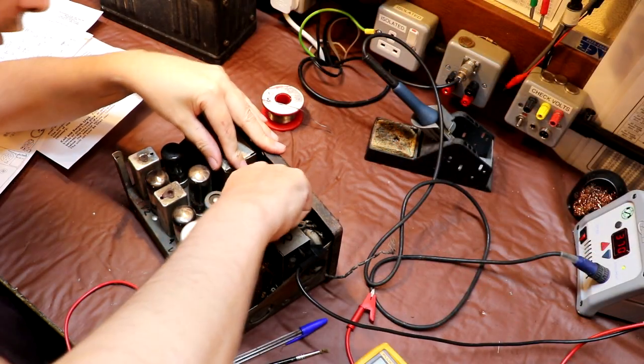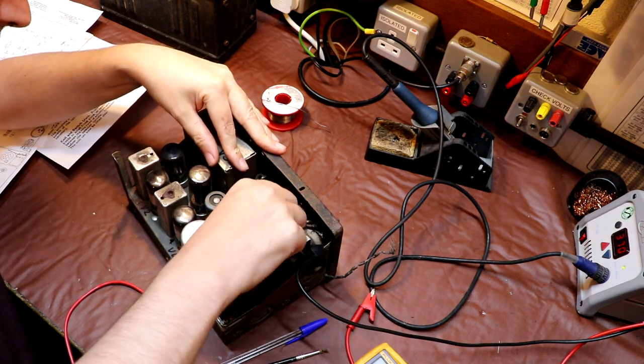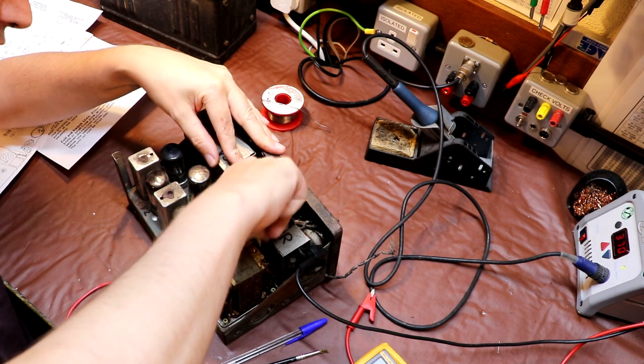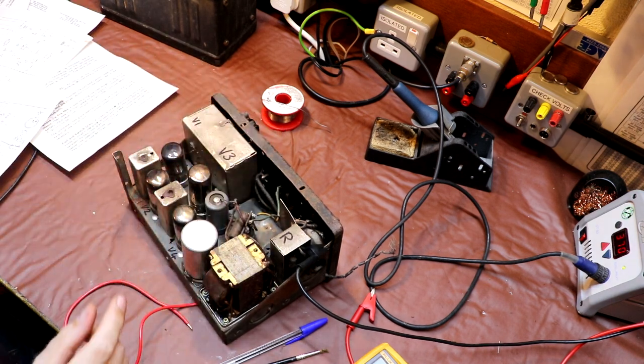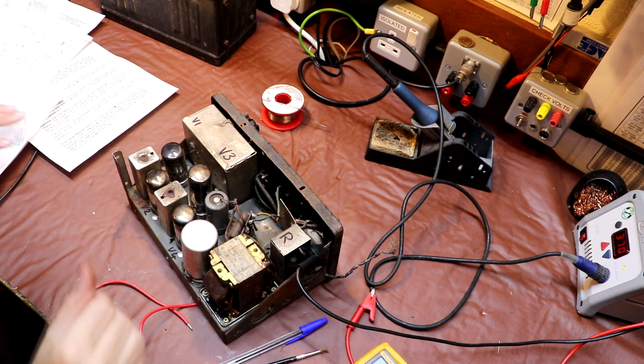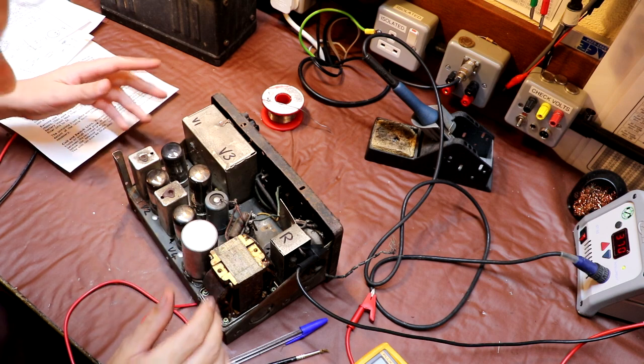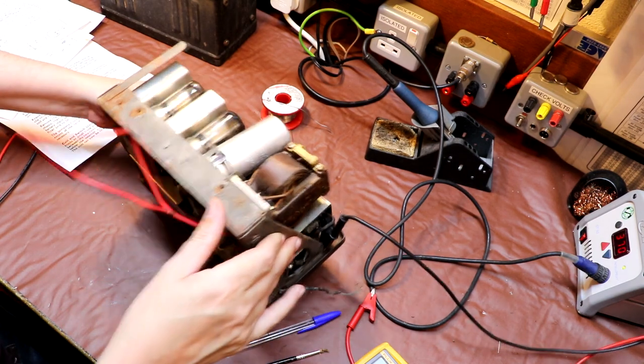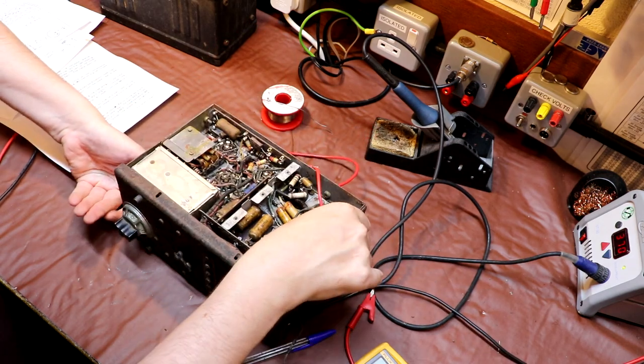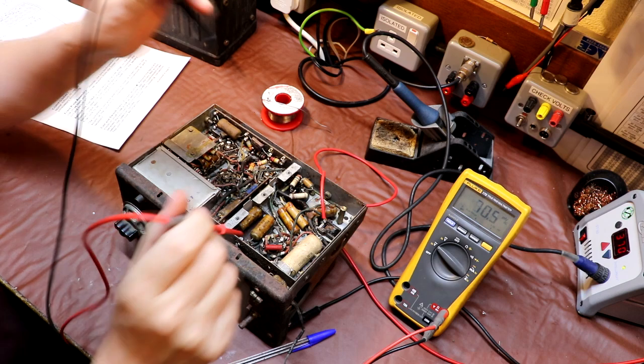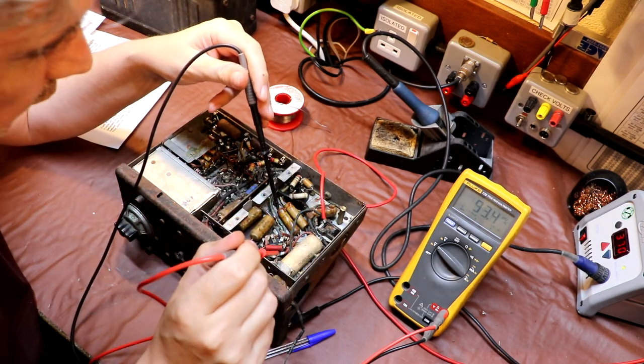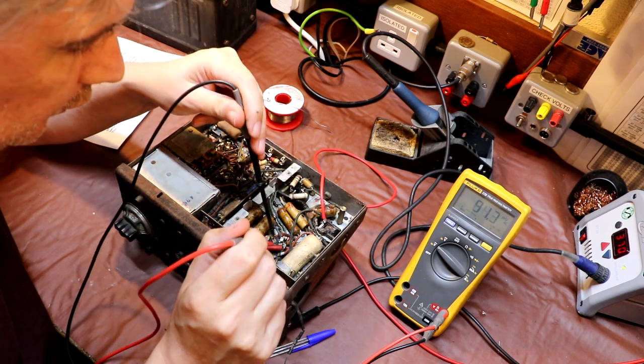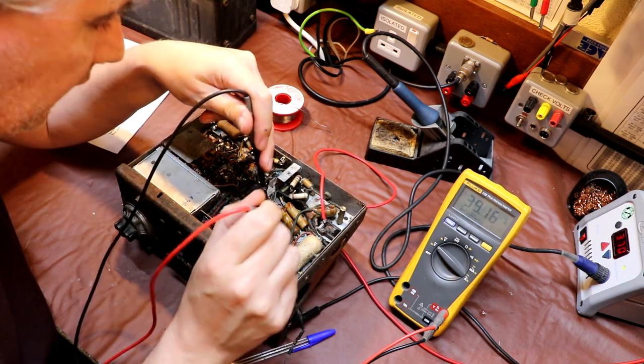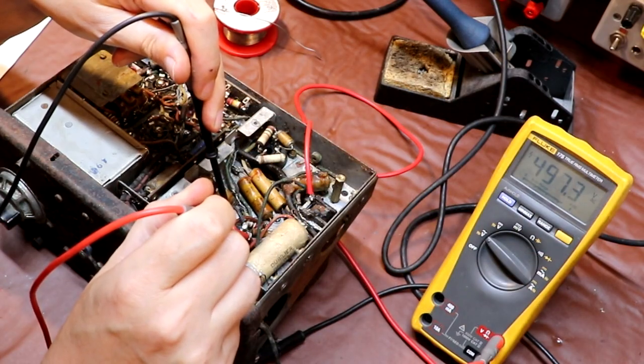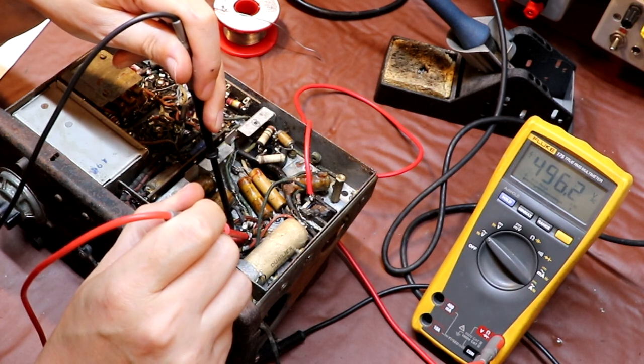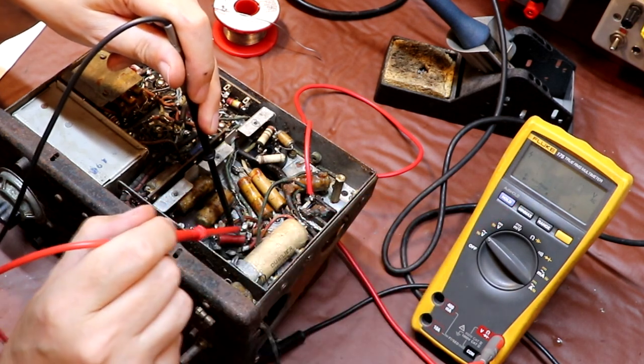I think what I'll try doing is pull the rectifier tube out, and we'll just have a look at the AC coming into the anode of the valve, because I think the HT needs to be a couple hundred volts for this radio. So I guess we're looking for more than that on our anodes - let me just see if we can measure that. We're not going to be producing any DC now because we pulled the rectifier, so I think we can just go off the anodes, which I think is that one. Good, so there we go, we've got 500 volts - so we've gone from 12 to 500 volts. Hopefully you can see that.